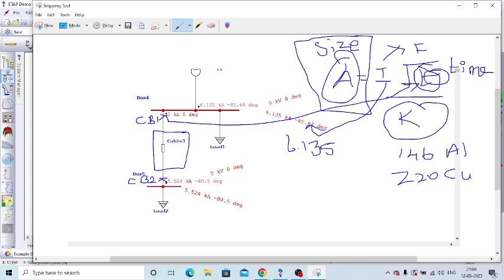6.135. Okay, so if it is aluminum cable 146 and copper cable 220, I is the fault current, and time t is the circuit breaker operating time. So normally it will be 0.4 second or 0.6 seconds, so based on the coordination curve, this time depends. Based on that we have to calculate the minimum size. So what is the size, the square area, that is coming? The selected cable in this location has to be equal to this size or a higher size, so that the particular cable can withstand this fault current.